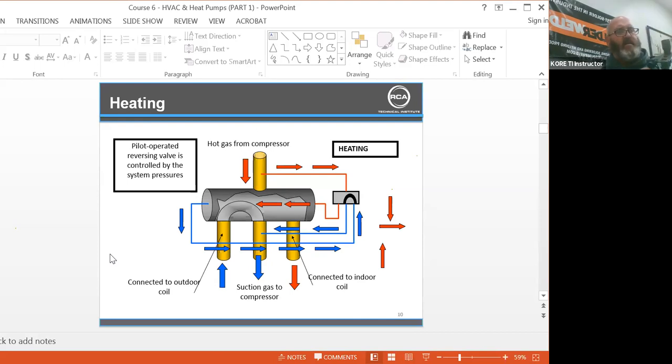Here's actually a little bit better diagram. This is a steel reversing valve coming out of a Trane package unit from the early 90s. This is solid steel that was taken out. You can really see these tubes that are used for controlling the slides on this one. It's really defined. This is a beautiful reversing valve. They're no longer made in this heavy duty steel. Most are in a brass body, but you can really see it.